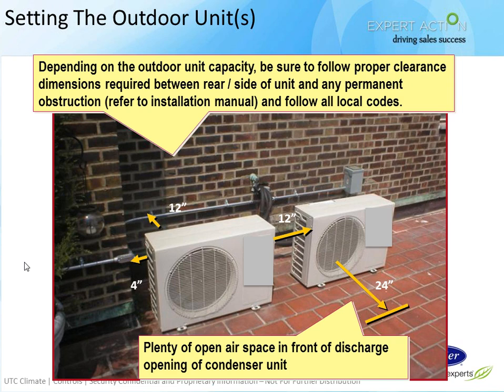Going to some installation tips. Outdoor units should be mounted level and on a solid surface. Proper clearance, you can see that we have 12 inches in between units and pretty much 12 inches all the way around. One thing to be careful about here, any heat pump unit will go into defrost cycle in the heating mode during the winter. That will create condensate, which may drain onto this walkway here. So be careful where you locate it so you don't create a slick spot that might be a hazard for pedestrians. Leave plenty of open space in front of the discharge of the condenser unit, and it should operate just fine.